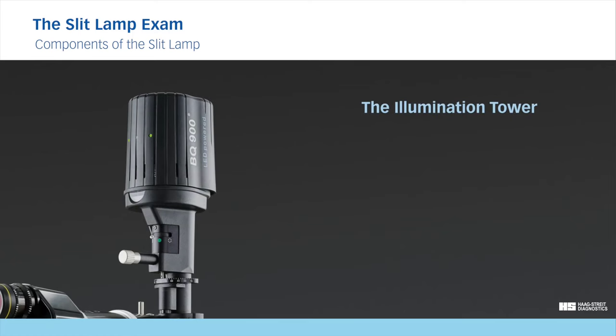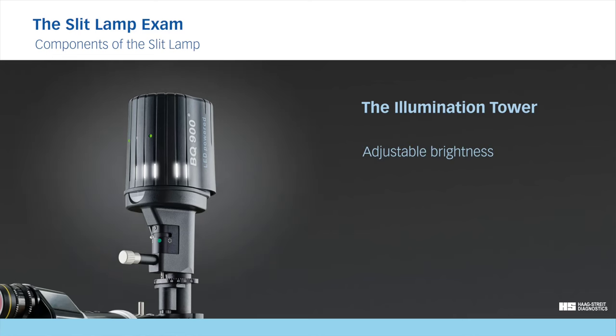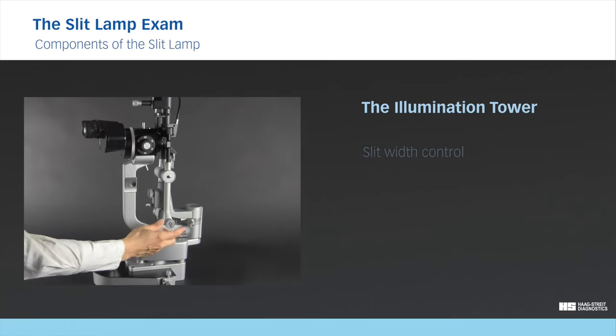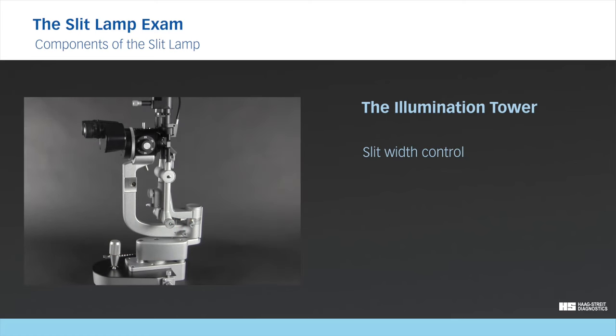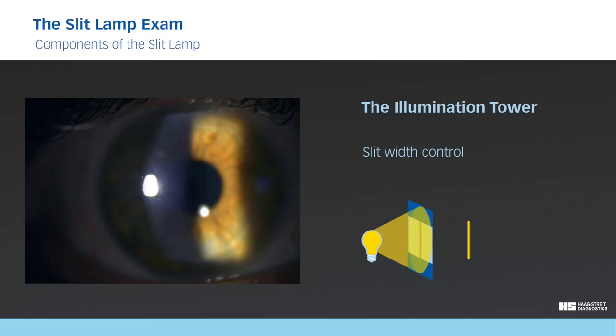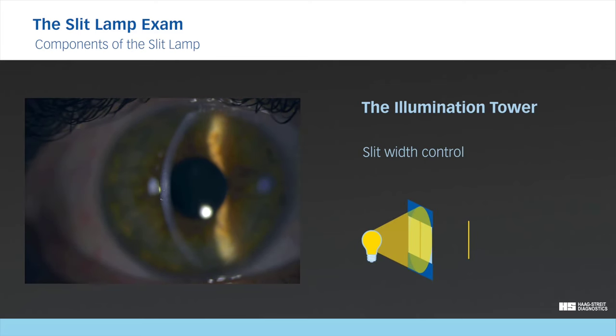The Illumination Tower. Central to any slit lamp is a powerful light source providing a well-balanced light spectrum that can be adjusted to the required intensity. Besides the light source itself, the main component of the illumination tower is an adjustable slit aperture within the illumination head. By simply turning the slit width control, the beam can be adjusted from wide to extremely narrow. This is important when examining semi-transparent structures in the eye without missing the necessary details.